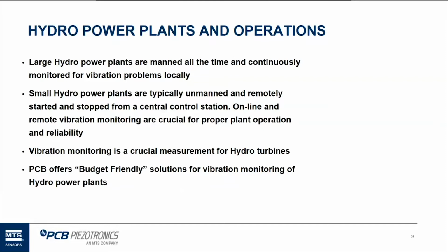I've seen smaller plants, and even today they exist, where the plant goes offline because of high vibration, but it went offline because it actually crashed. It didn't go offline because it was shut down because of high vibration. It crashed, which costs a lot of money to repair. And in some of these locations, it's very expensive to get equipment to do a repair on a hydro unit. So it's very crucial for all hydro turbines to have vibration monitoring. We have budget-friendly vibration monitoring solutions for smaller hydro plants, and also larger hydro plants if necessary that still don't have a good monitoring system for vibration.